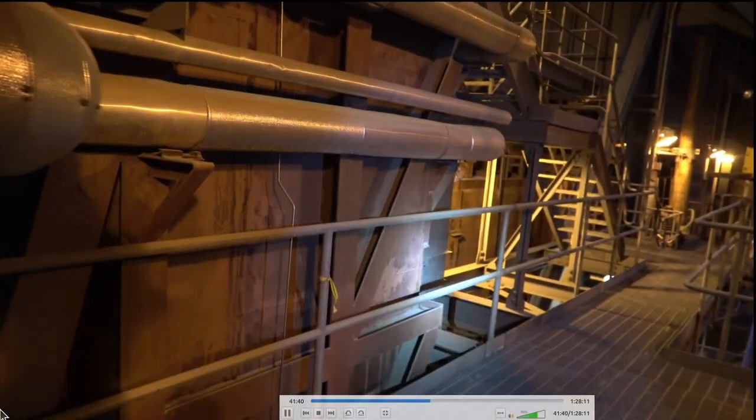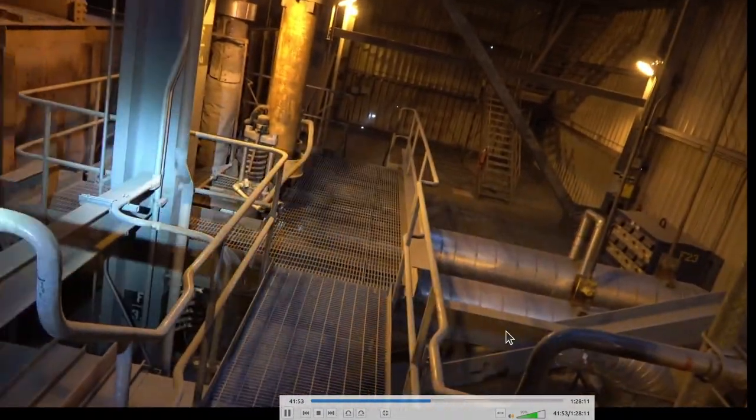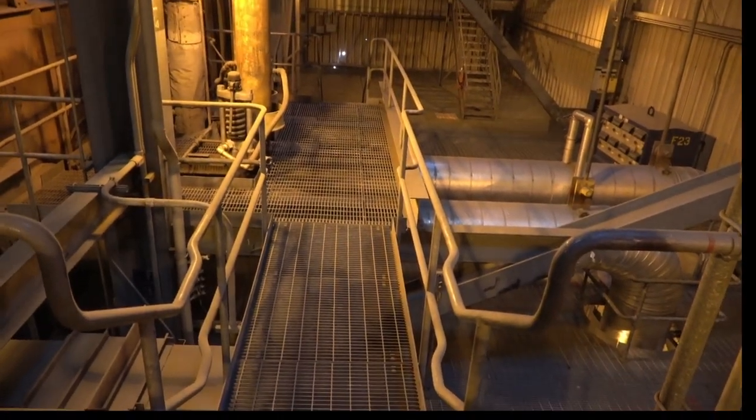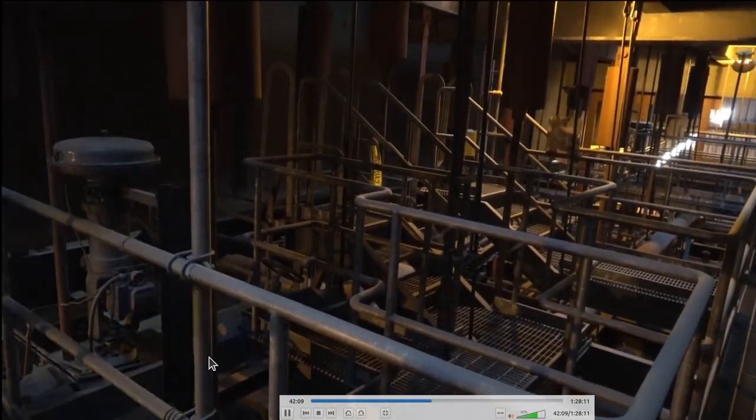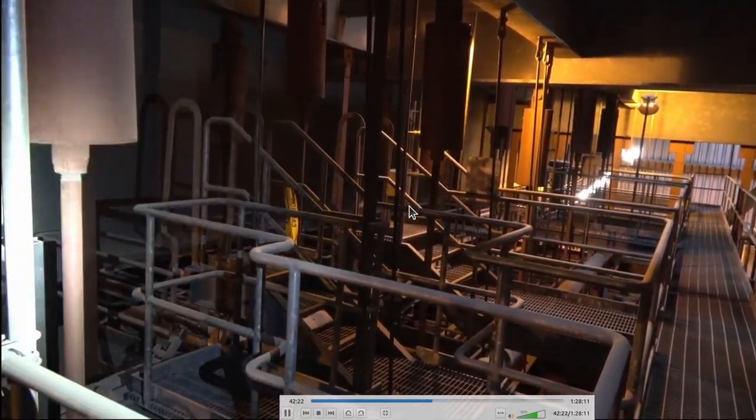These are the boiler safeties — these will go last. The first ones to blow are right off the boiler. There are electromatic valves that go first to keep steam flow through the boiler. You use your outlet valves — they're designed to go first to maintain steam flow through the superheater. You have two steam lines that come out and connect to one further down. Back here is called the penthouse — inside is all the connections for the division walls and superheat platens. This is one of the superheat finishing sprays — it maintains 1,005 degrees on the outlet. It sprays before the superheater so there's no moisture getting through it. These are set to about 1,005 outlet — at lower loads they'll be a little bit less.